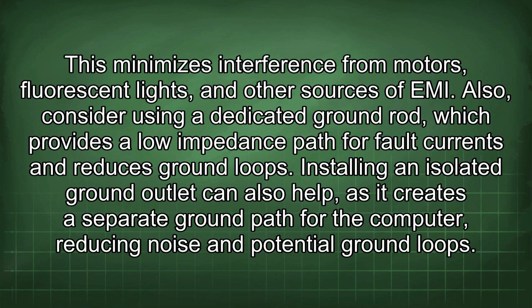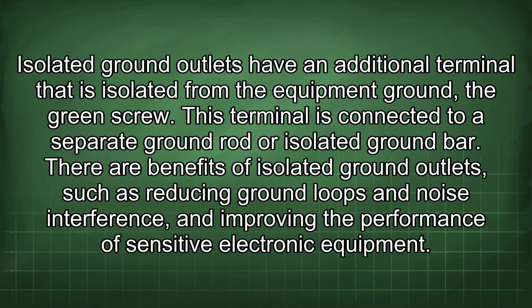Also, consider using a dedicated ground rod, which provides a low impedance path for fault currents and reduces ground loops. Installing an isolated ground outlet can also help, as it creates a separate ground path for the computer, reducing noise and potential ground loops. Isolated ground outlets have an additional terminal that is isolated from the equipment ground, the green screw. This terminal is connected to a separate ground rod or isolated ground bar.